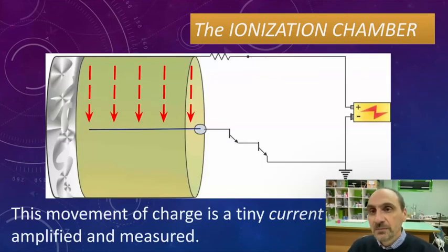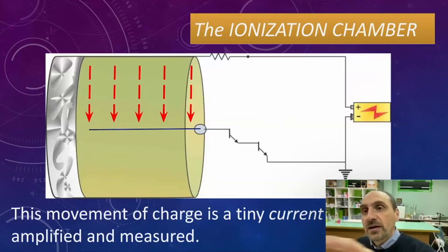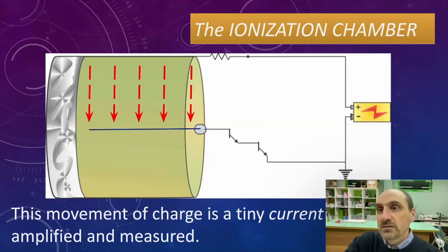This is the scheme of a project. You can see on the left the ion chamber. And if I apply a voltage, I have a power source, a battery. If I apply this voltage, the electrons will be collected and the tiny current will take place. Of course, this current is really tiny. I mean, femtoampere, meaning that it's about thousands of electrons per second. And we have to measure this tiny current.